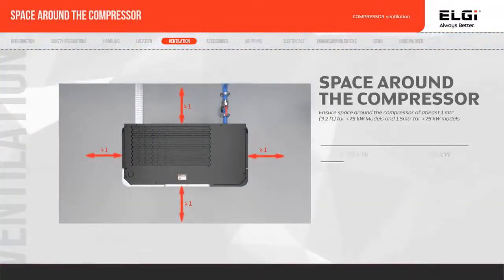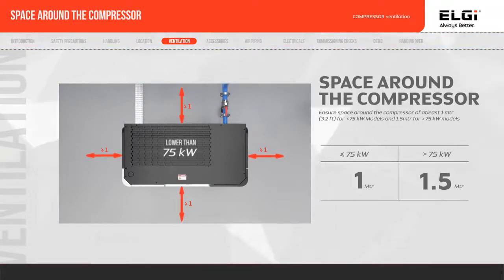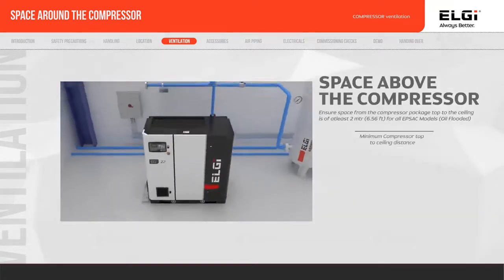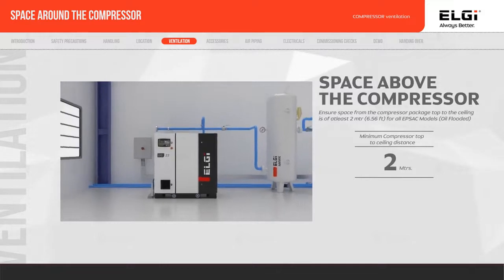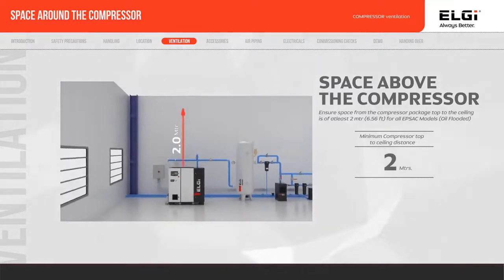Ensure space around the compressor should be 1 meter, 3.28 feet, up to 75 kilowatt or below, and 1.5 meters, 4.92 feet, for above 75 kilowatt models. Ensure space from compressor package top to ceiling is 2 meters, 6.56 feet, for all EPSAC models, oil flooded.